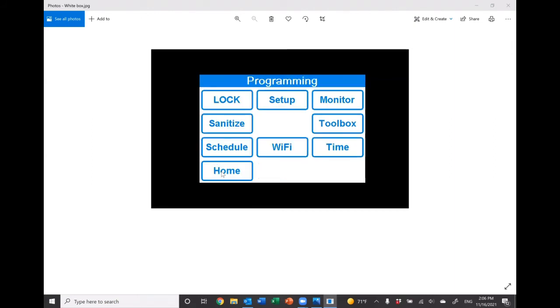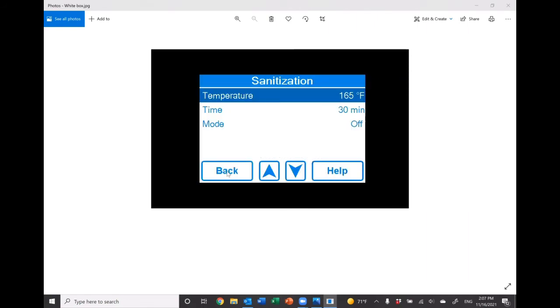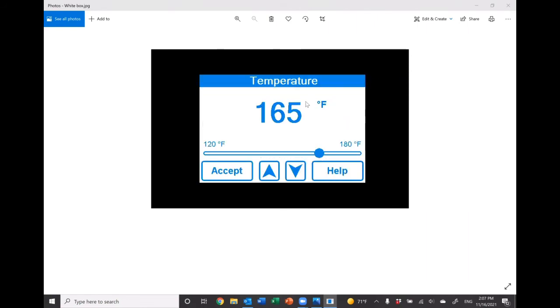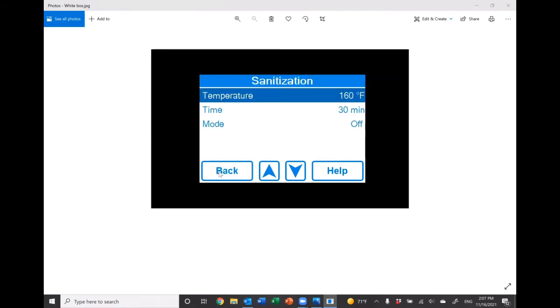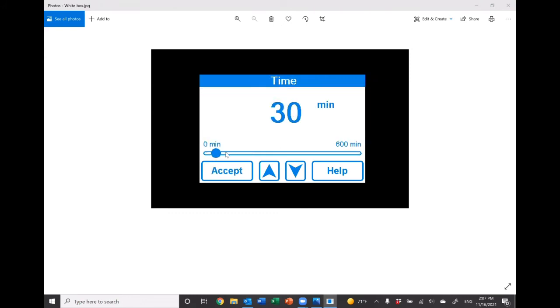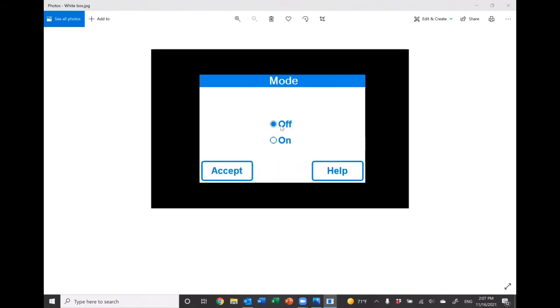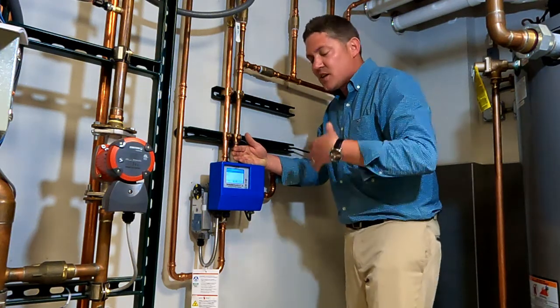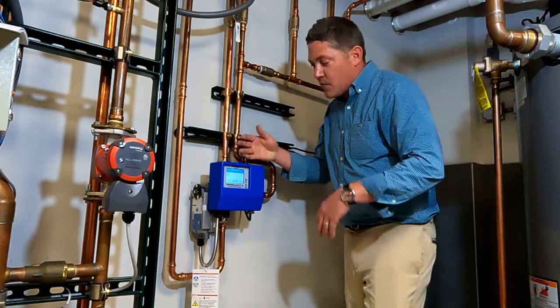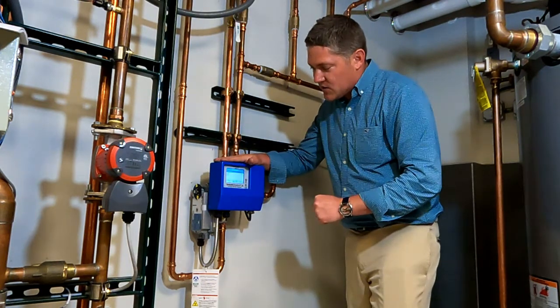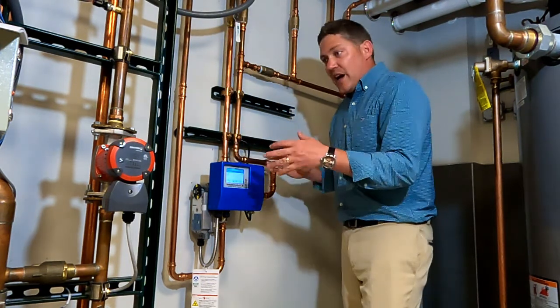Once you've got it all set up, ready to go, it also has the sanitization mode, so if you're doing a sanitization for the building, you can go right in, hit sanitization, and pick the temperature and how long. So let's say we wanted to run it for 160 degrees for 30 minutes. We set 160 degrees, 30 minutes, go. It'll raise that temperature up to whatever you have it at, as long as the supply temperature can reach that temperature, and then it'll start that countdown of my 30-minute timer in this case. Once it reaches the end of the 30-minute timer, it'll go right back to the settings that were originally in it. Aside from that, it's just like the Senior.